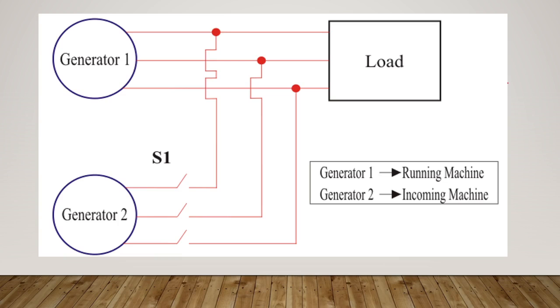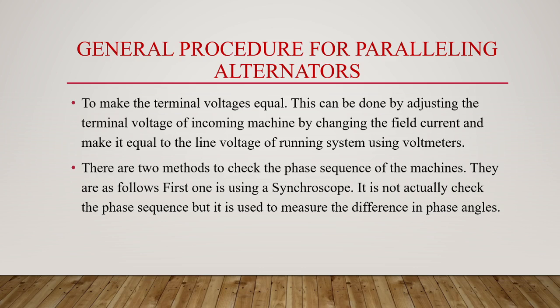So these two generators are connected in parallel and connected to a load. Generator 1 is a running machine, generator 2 is the incoming machine. To make the terminal voltage equal is one condition. This can be done by adjusting the terminal voltage of the incoming machine by changing the field current and making it equal to the line voltage of the running system using voltmeters.